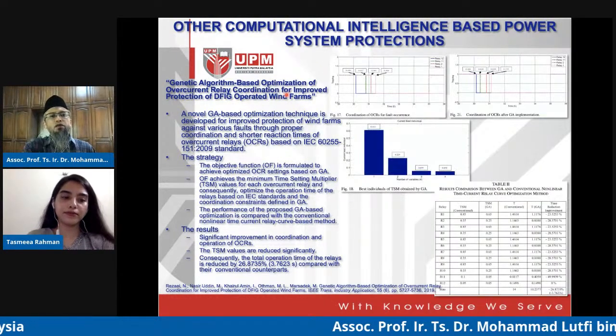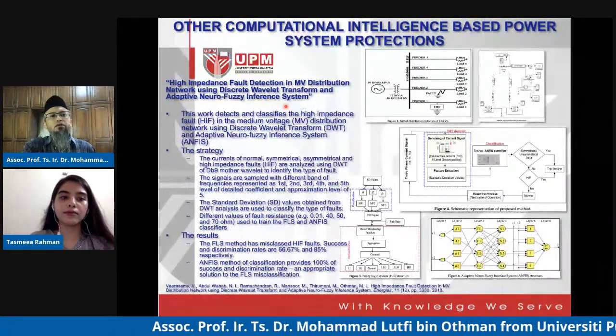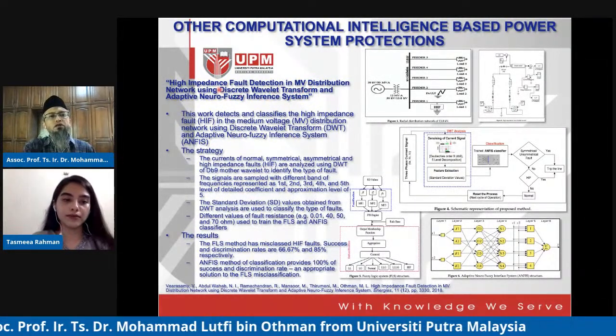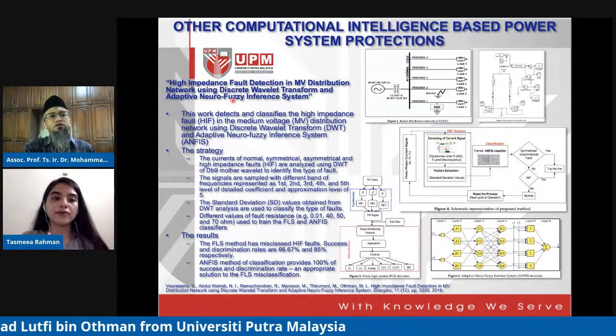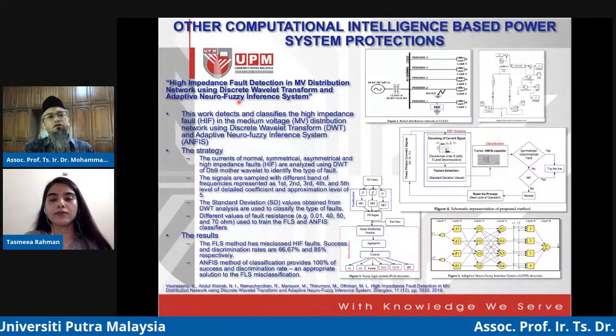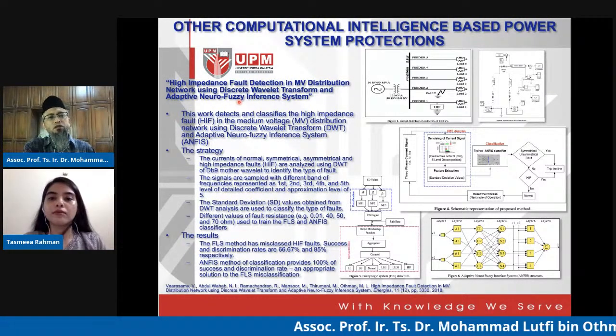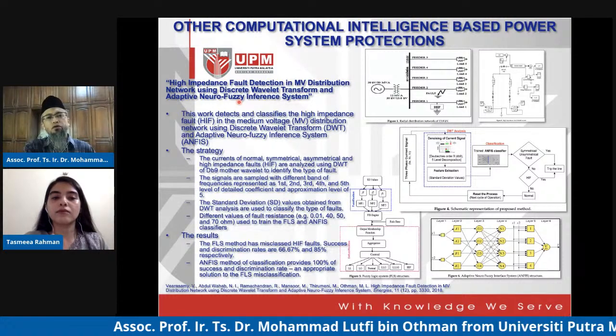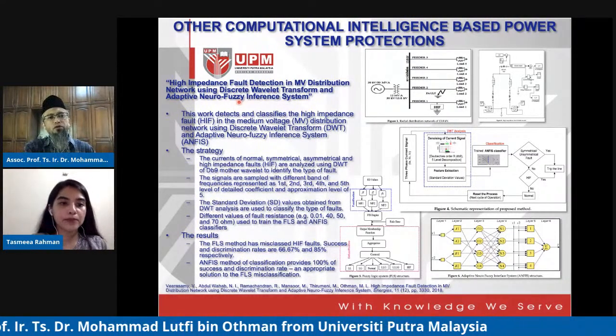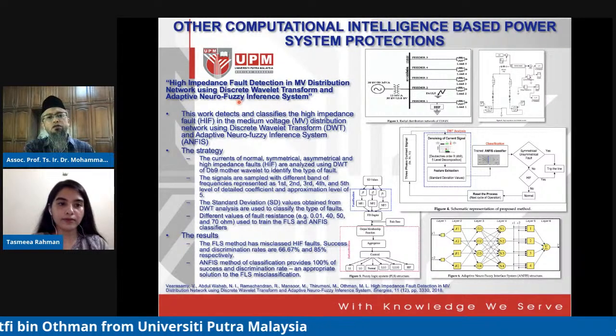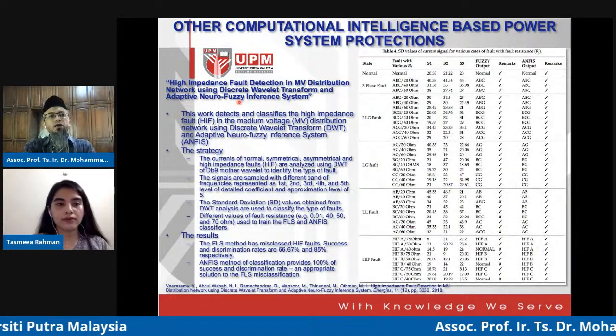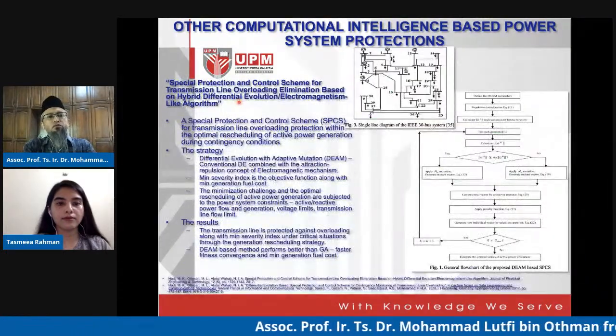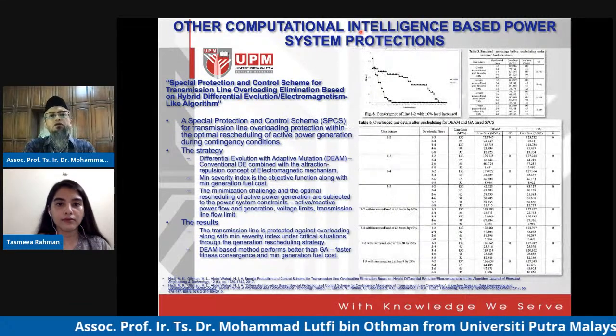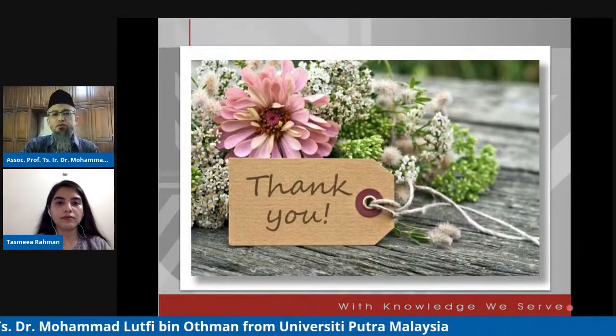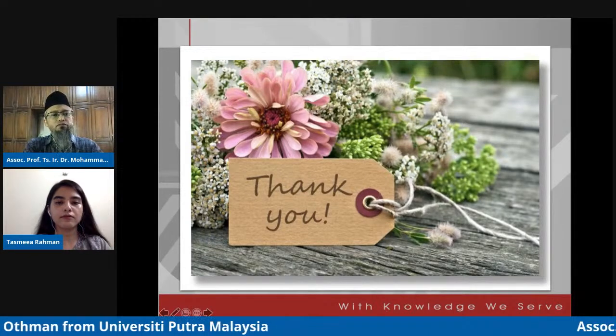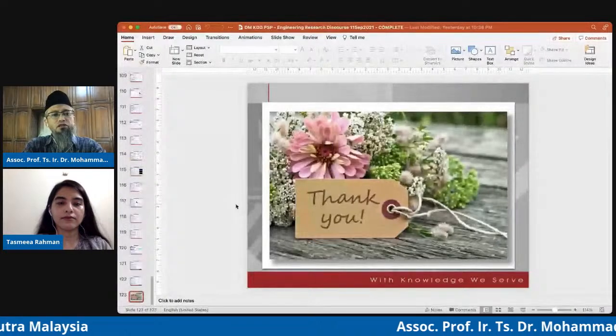So we use genetic algorithm, and we have used a combination of wavelet signal processing with ANFIS to deal with the high impedance fault. High impedance fault is something very peculiar because, however good the relay is, it fails to operate because of the low current detected by the relay when the high impedance fault is in place. And we have many other works that we have done using computational intelligence in dealing with the power protection system. So with that, I pretty much end my presentation.